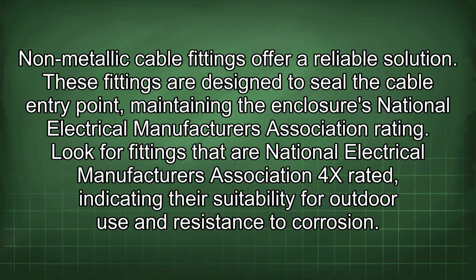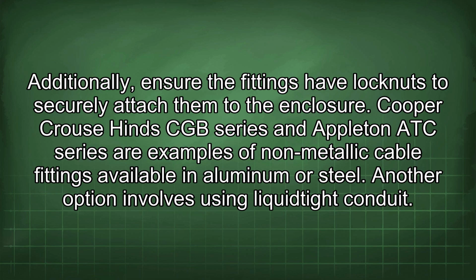Non-metallic cable fittings offer a reliable solution. These fittings are designed to seal the cable entry point, maintaining the enclosure's National Electrical Manufacturers Association rating. Look for fittings that are National Electrical Manufacturers Association 4X rated, indicating their suitability for outdoor use and resistance to corrosion. Additionally, ensure the fittings have lock nuts to securely attach them to the enclosure. Cooper Crouse-Hinds CGB series and Appleton ATC series are examples of non-metallic cable fittings available in aluminum or steel.